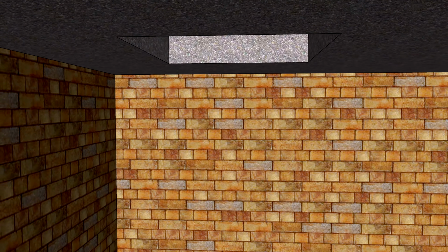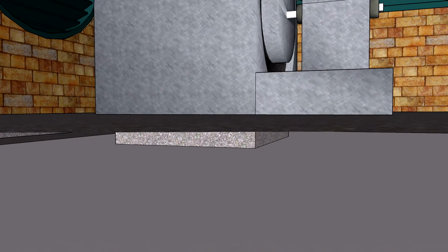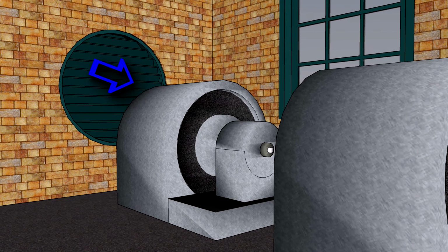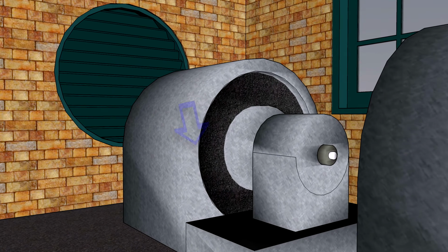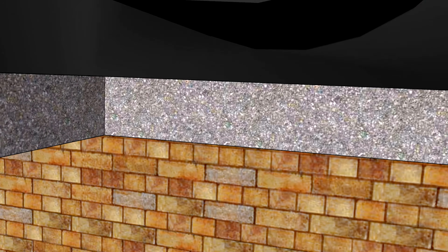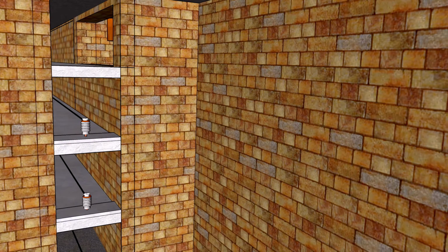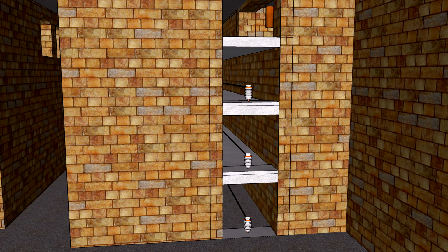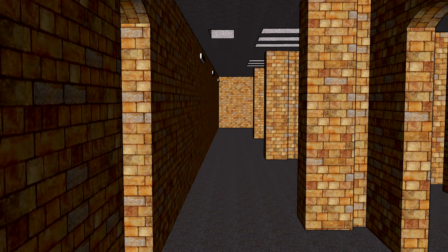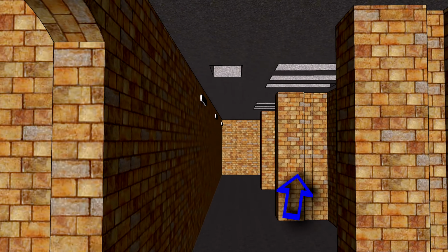The basement was effectively designed to be airtight. Large blowers on the first floor pushed air from outside the building into the labyrinthine basement, maintaining a positive air pressure in the sealed basement. That positive air pressure was then pushed up through large holes in the main floor directly underneath the substation machinery, bathing the machines in a continuous stream of air cooled by the lower temperatures of the earthen basement.